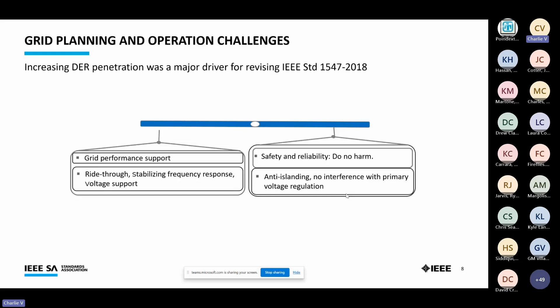A big other change going from the 2003 to 2018 version of IEEE 1547 was the inclusion of interoperability. There was a question in advance about communication protocols—in the interoperability section, it calls out four specific protocols that, through your Rule 5.5 referencing the latest 1547 version, inherently requires use of core protocols common across the power industry as a capability. Now it's up to the AHJs, the connecting utilities, to determine which protocols go from capability to requirement, so that's something for your community to work through.